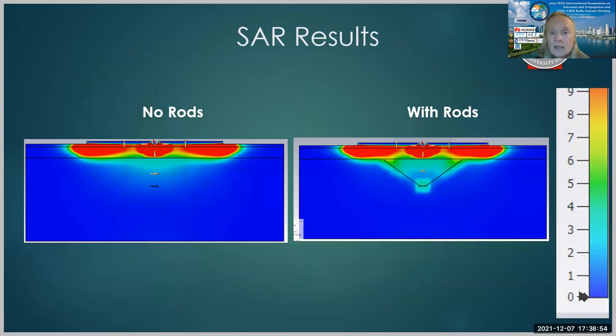And then here are the patterns of energy. So here are the SAR patterns. And you can see with no rods, the energy is concentrated under the dipole. But with rods, we're able to get much more power down to the implantable medical device.